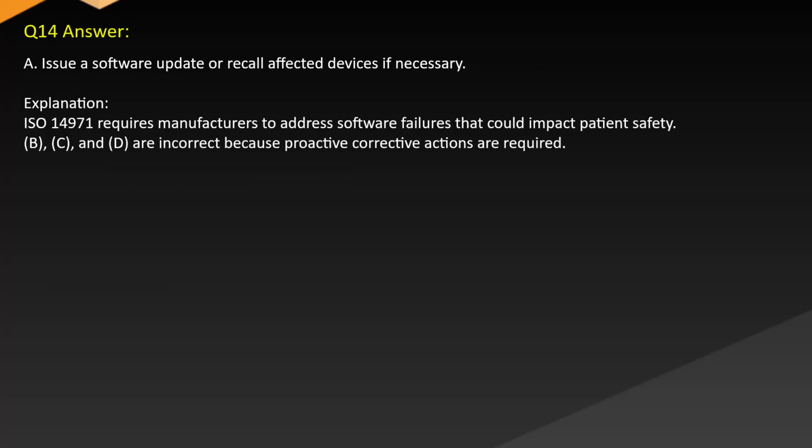Answer A. Issue a software update or recall affected devices if necessary. Explanation: ISO 14971 requires manufacturers to address software failures that could impact patient safety. B, C, and D are incorrect because proactive corrective actions are required.